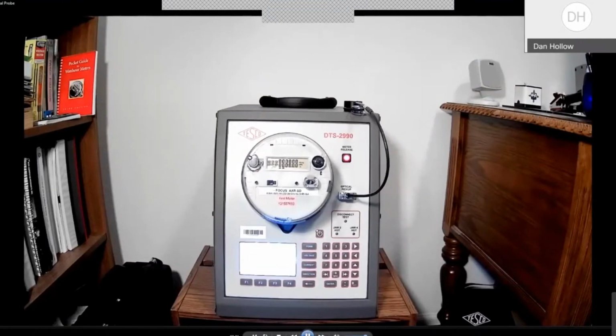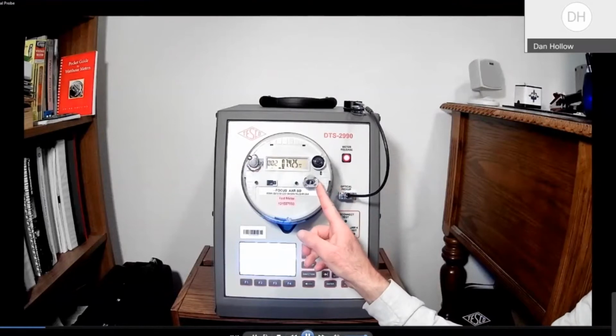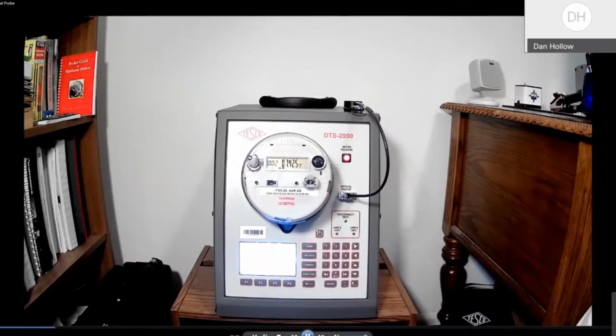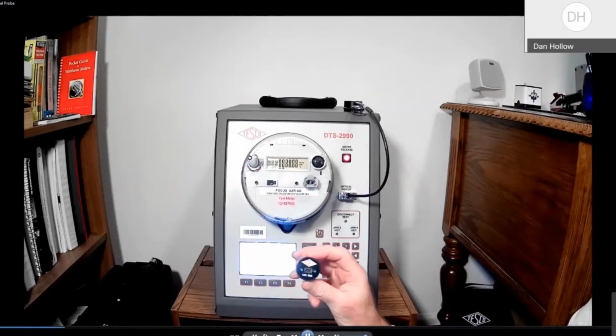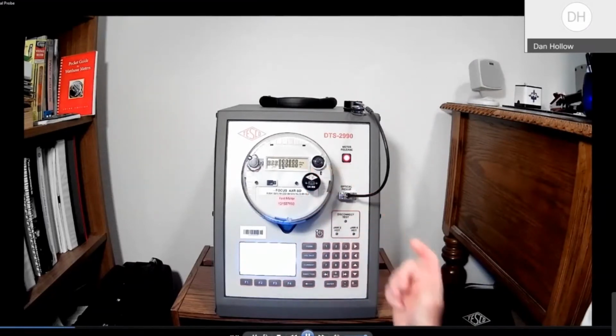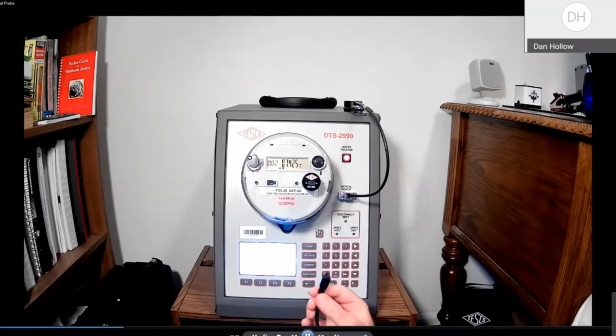For this segment of today's presentation, we're going to demonstrate an optical probe. Optical probes are used for two-way communications between typically the vendor software and the meter through the optical port on the meter. Optical ports typically have a metal plate for the magnet in the optical probe head to adhere to. So we're going to go ahead and put that on there. If they do not have the metal plate for the magnet to stick to, then we make adapters that will go on there and give it that metal plate. Then the cable is just an off-the-shelf USB to mini USB cable.